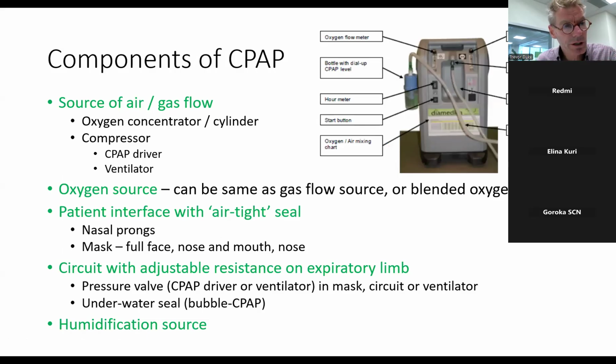Any CPAP machine has some basic components, and I think it's important that we all understand what those components are. Firstly, you need a source of gas flow, and if it's a ventilator, then the ventilator is a source of the gas flow. If it's a CPAP driver, a CPAP machine, then the CPAP is the source of gas flow. In the oxygen concentrators, these Diamedica machines, it's the grey one, not the black one I showed you before. The concentrator is the source of gas flow, and that produces, as I said, both oxygen and air, and there's one flow meter that produces oxygen and one flow meter that produces air.